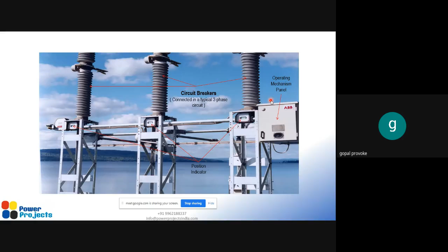And we will be having a current transformer. So the main application of current transformer: if it is a low voltage system like a 415-volt system or a single phase 230-volt system, we will be having an energy meter which will be connected directly to the supply, so that we can measure the current to measure the amount of units or energy consumed. But in case of a high voltage substation, we will not be able to measure the current directly. If it is high voltages like 33 kV or 110 kV, we have various voltage ranges, 230 kV, 400 kV. So in case of such high voltage substations, we need a mechanism for stepping down the current. That particular equipment is called a current transformer.